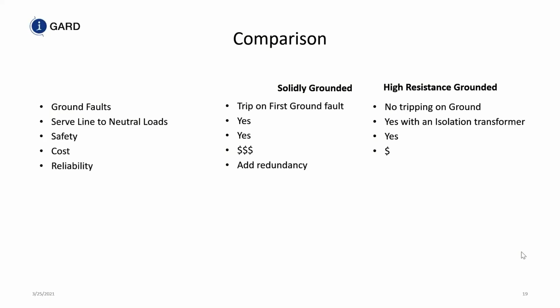Reliability. With the solidly grounded system in data centers, because we understand that when you get a ground fault, it is understood that you must trip. We tend to put in more redundancy. And just because you end up putting more redundancy in a system doesn't make it more reliable. It just means you have more things that can fail. Adding redundancy does not increase reliability.